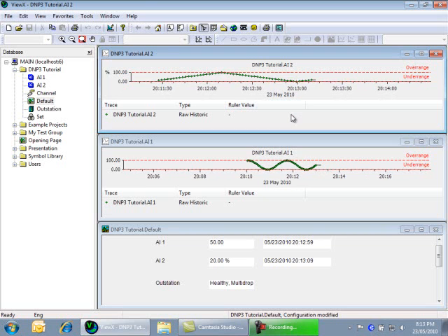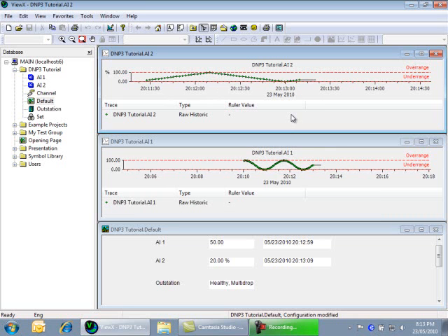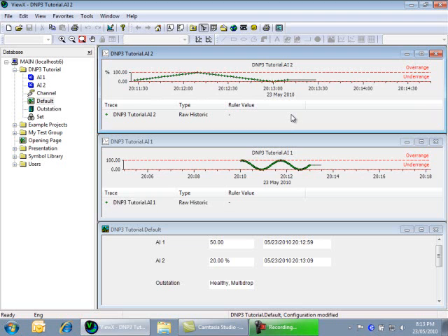After some time, Clear SCADA will raise a communications failed alarm. The time to raise this alarm depends on how frequently you poll the device, the comm retries configured, the number of transaction attempts, and the way that the failure occurs. All these settings are configurable to provide flexibility in the way that comms problems are reported to users.